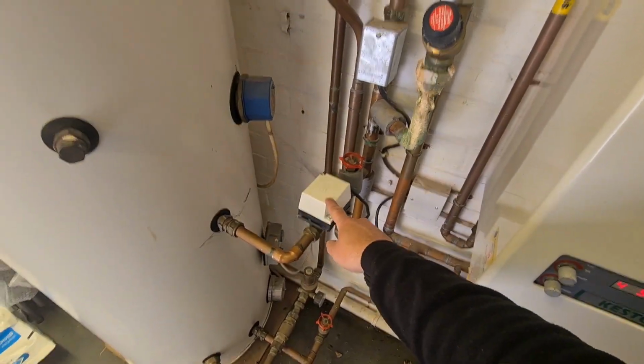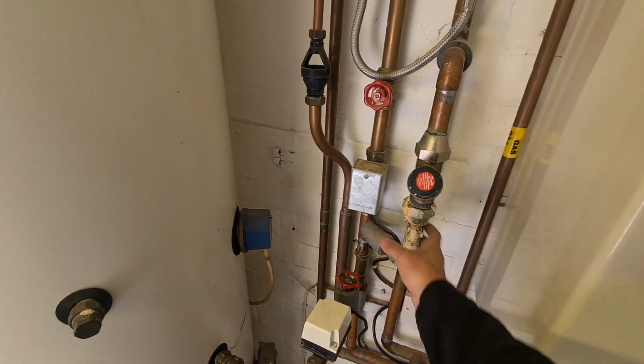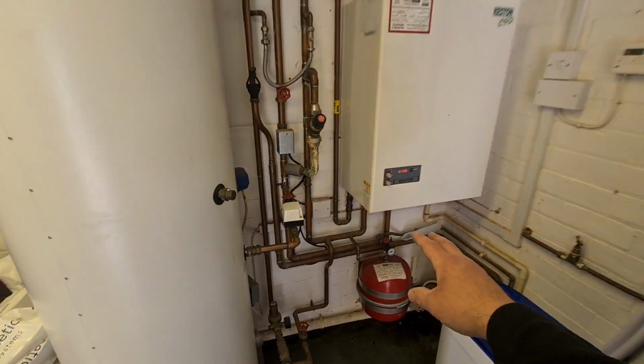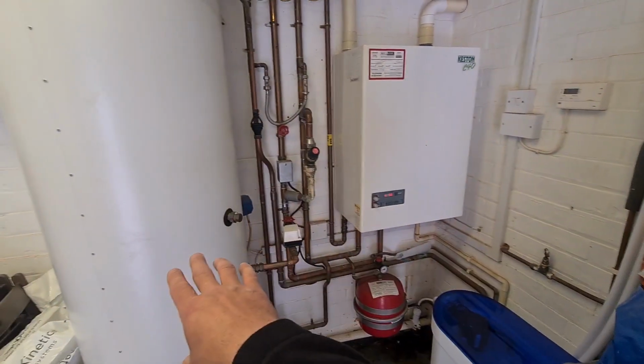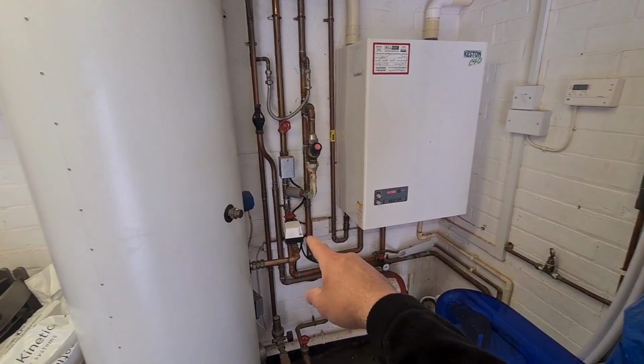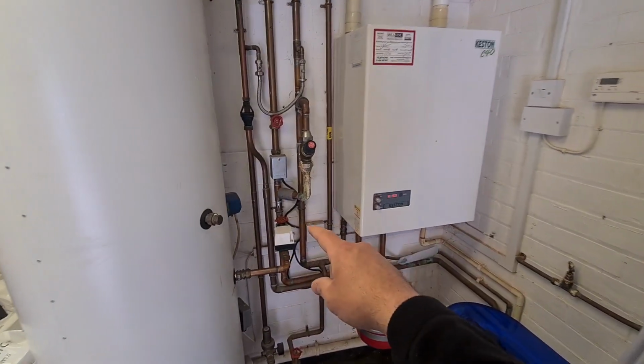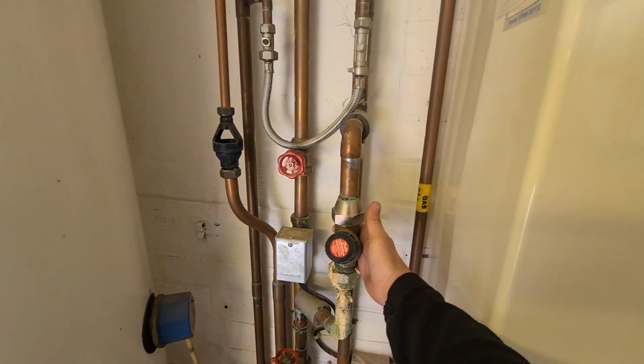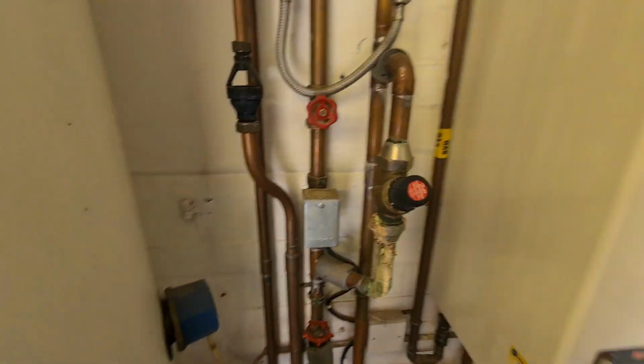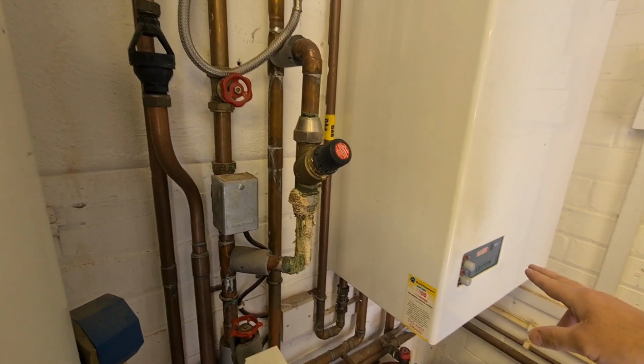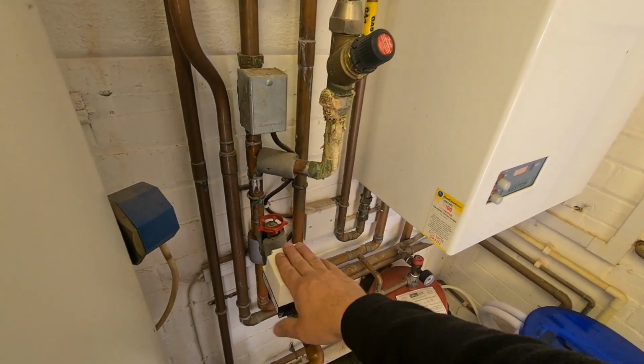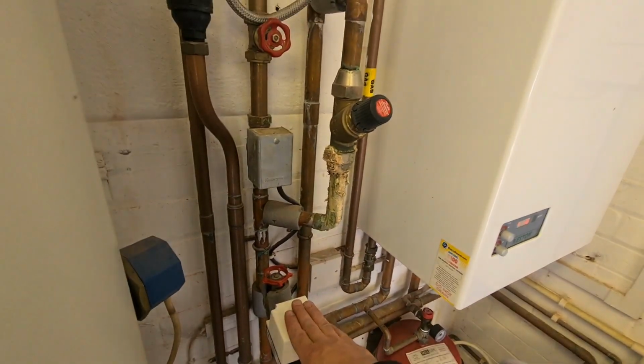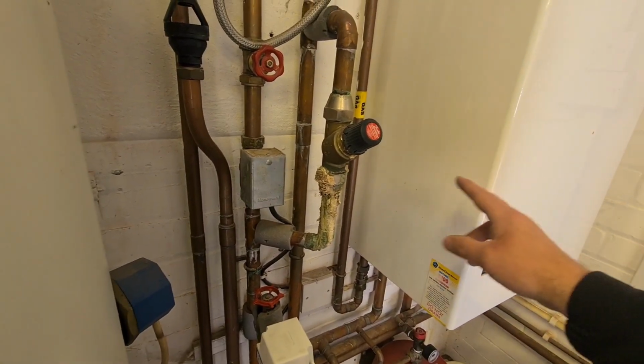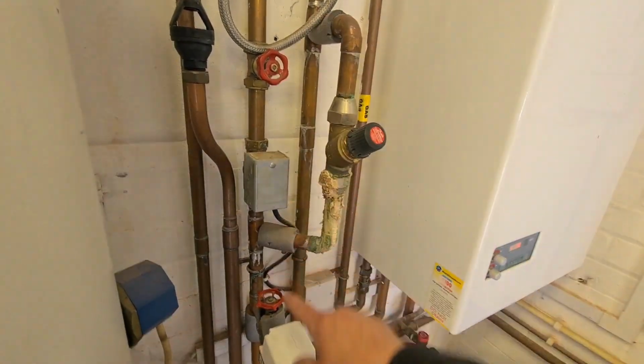We've got a hot water zone valve there and a heating zone valve there with the bypass. So what is happening with this job here is, whenever my heating or hot water come into demand, the boiler will fire up. Each zone valve will open independently. But what I'm finding is this valve here, which is the bypass. The reason we install a bypass is because when these valves shut down, we don't get water pump hammer, should I say, in the system. Also the pump can get the heat away from the heat exchanger. It just creates a constant circuit around this little 2 or 3 metres of pipework here.